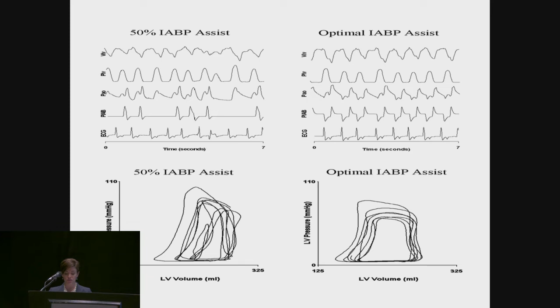The timing in this example on the right is using WAVE and R-wave deflation, so it's truly automatic beat-to-beat, intra-beat timing. While there is still some variation in stroke volume on a beat-to-beat basis due to rate and filling time changes, the overall contraction of the LV is more uniform with fully timed inflation and deflation. Now, to conclude for today, we have confirmed that the balloon pump produces an immediate and predictable improvement in LV performance within the first 3 to 4 beats of properly timed full assist support.